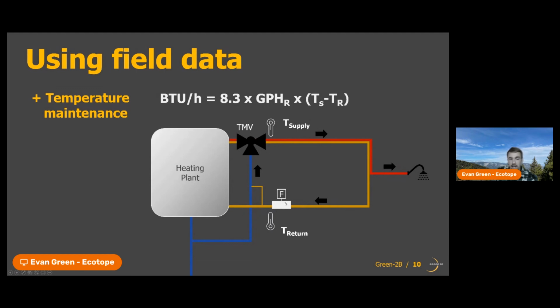You'll just need to make sure you capture the flow before it splits back off into the cold water line that typically goes through the mixing valve. And so once we have that flow and that differential temperature, we can calculate the total BTUs lost by using this equation: 8.3 times gallons per hour of total temperature maintenance flow, times that temperature difference between supply and return.